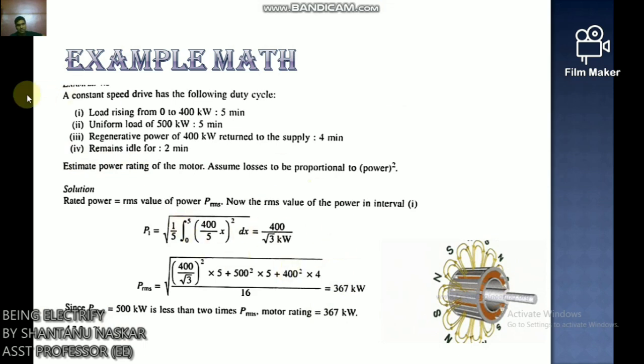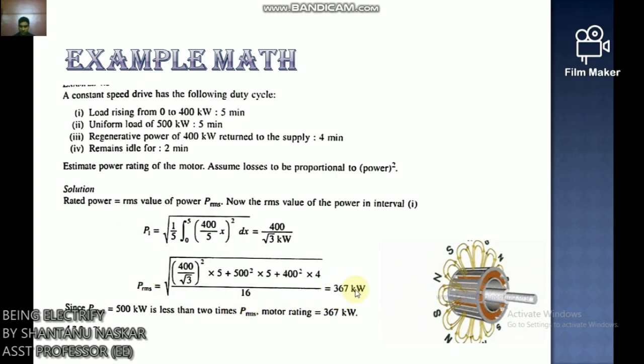Example: A constant speed drive has the following duty cycle — load rising from 0 to 400 kW over 5 minutes; load of 500 kW for 5 minutes; regenerative power of 400 kW for 4 minutes; idle for 2 minutes. Estimate the power rating of the motor assuming losses proportional to power squared. Solution: Rated power equals the RMS value of power, which computes to approximately 367 kW.